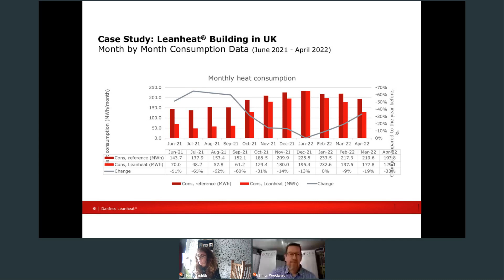So the data here is for around 11 months, and within 11 months of operating this software in these blocks, we saved 600 megawatt hours of heat, which equates to around 156 tons of CO2 and around a £24,000 value saving. These numbers are prior to the gas crisis that we find ourselves in today. So if you can imagine, if we installed this into a number of buildings now, how much of a financial saving that would provide building owners.